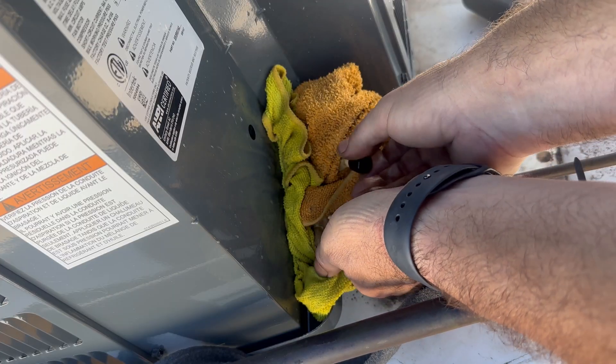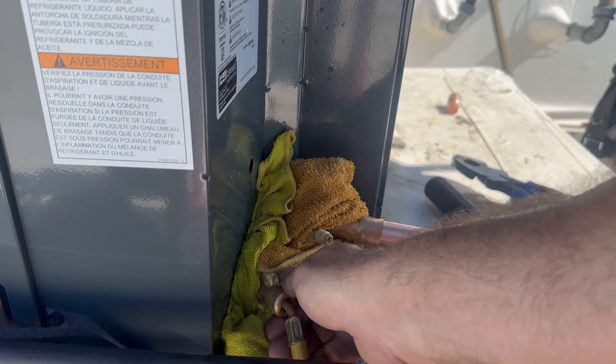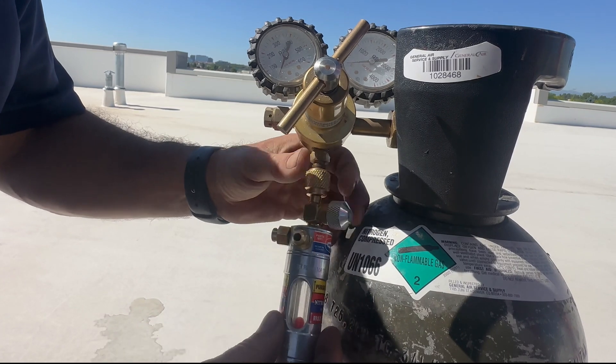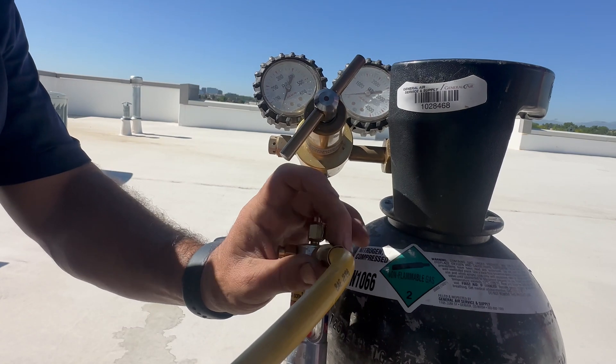Then I'm going to remove my valve caps, then my Schrader valve cores with my Appion valve core removal tools. Attach my refrigerant hose to the liquid line, then attach my NitroView flow indicator to my nitrogen regulator, then attach the refrigeration hose to the flow indicator.